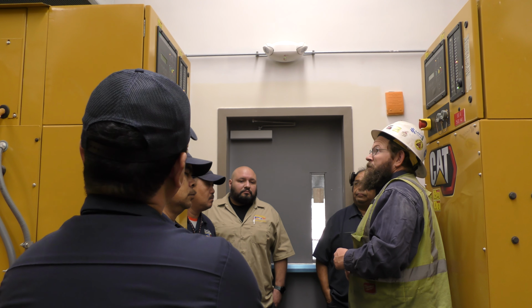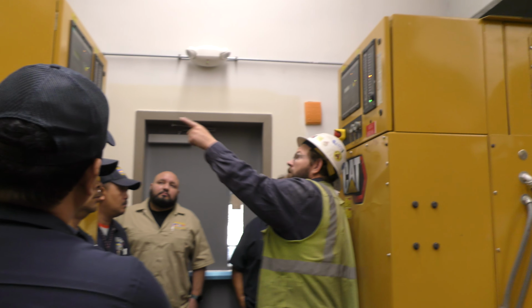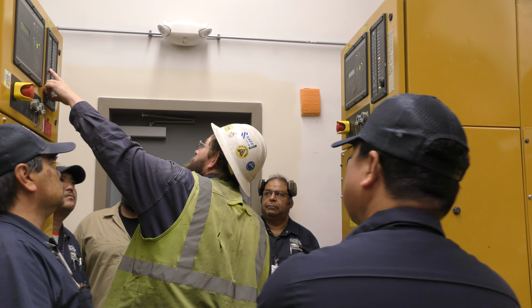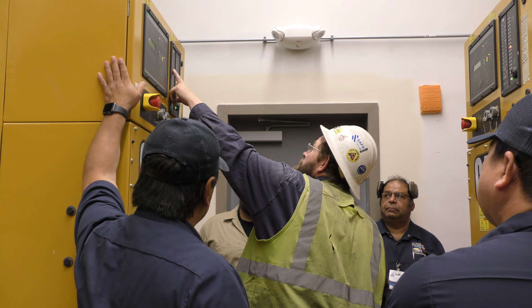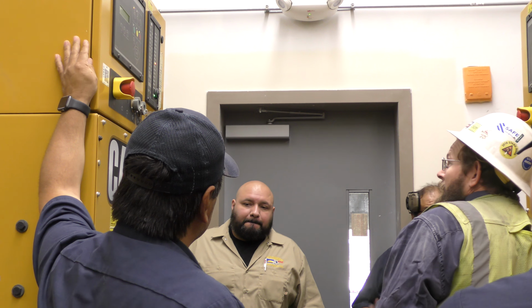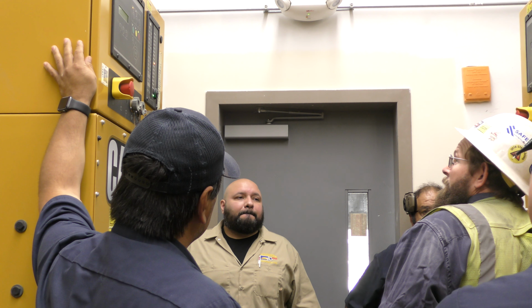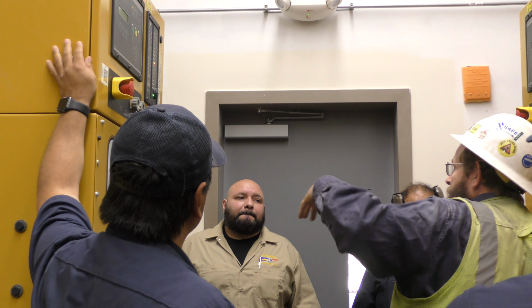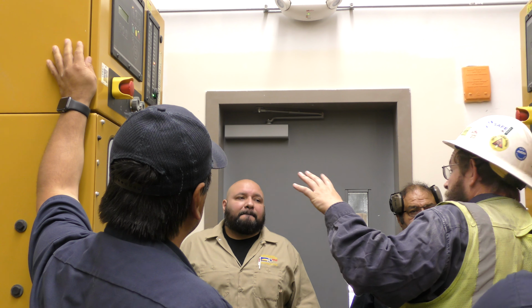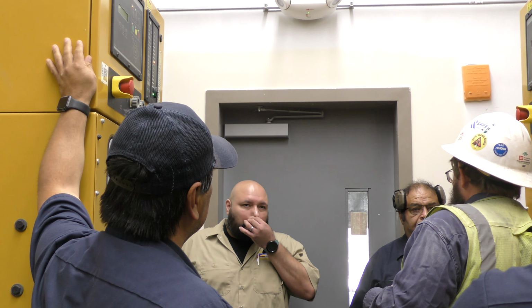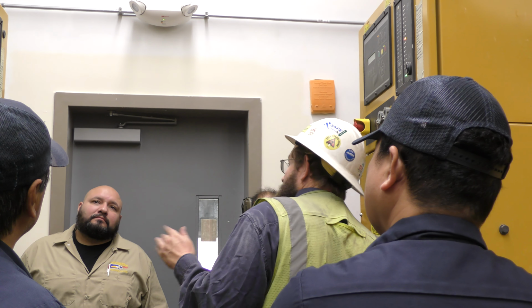If you lose power to the block heater, this temperature's going to start dropping. So you'll get a low coolant temperature alarm. Basically, that alarm won't stop it from starting; it's a warning. So if the block heater went bad and your coolant temp dropped below 70 degrees, it's going to tell you, hey, I'm low. But in an outage, it's still going to start and run. It's not going to shut off on a low coolant temperature alarm. It's just letting you know, hey, I'm lower than I should be, still functional. The only thing that's going to prevent it from starting is any shutdowns.